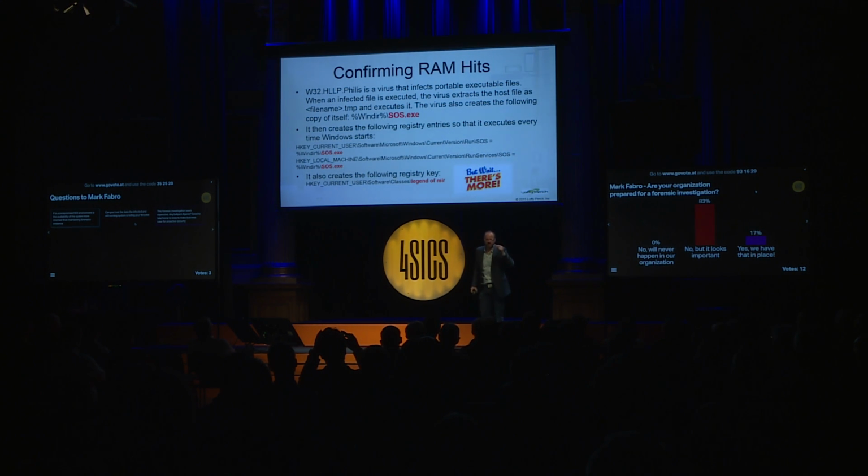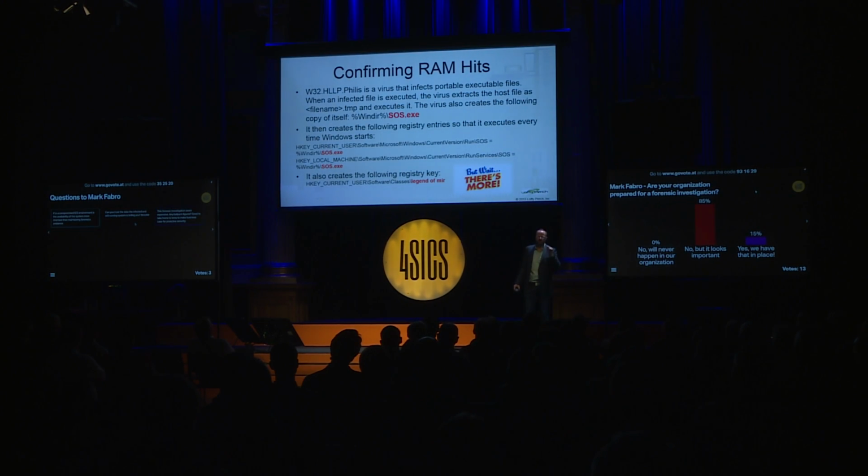Without the proper understanding of the applications in the software for the particular generation software, you fail to recognize that SOS.exe is a vendor-specific executable that is responsible for protocol translation. The removal of that executable will instantaneously bring everything to a grinding halt. Safety, point-to-point comms, engineering to HMI, HMI to database, everything. Right? It was not the virus.